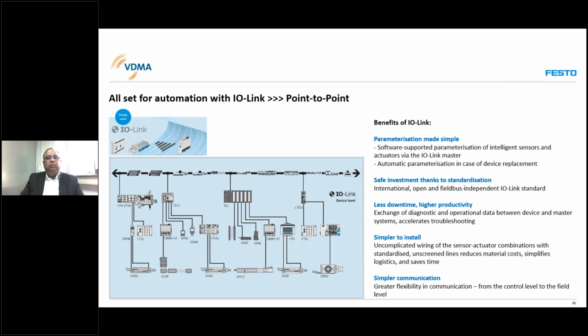With IO link being a point-to-point and bidirectional communication, this is not necessary. Directly, when all the parameters are loaded on the pressure sensor, the PLC, the controller, exactly knows what data is there on the pressure sensor. Then whatever changes need to be done can be done directly sitting in the office, and nobody needs to go to the field to touch the devices and change the parameters.